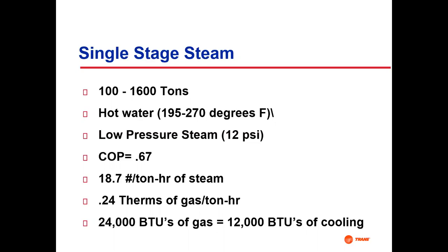Now, it's used for chillers because for an electric driven vapor compression cycle, it's almost always over one. So we get down here to the COP and it's less than one. So in this one, we could call it the efficiency. But on all the other ones, we can't. So it's still the COP. The COP is another term for efficiency when we expect the value to be over one.